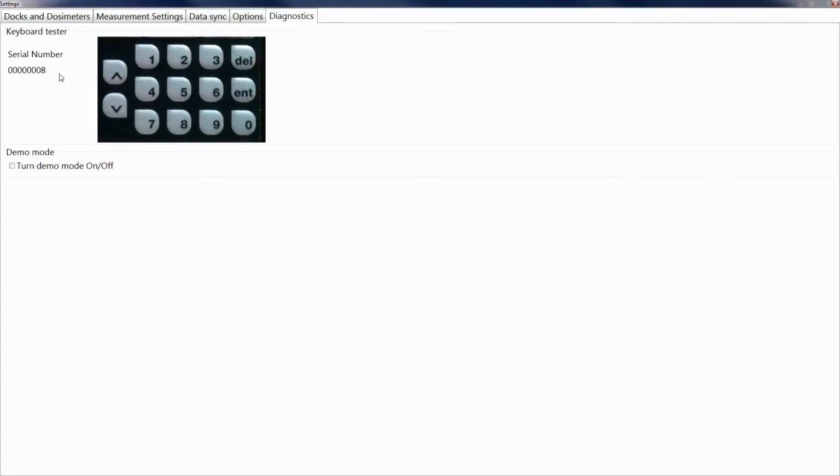The next option is demo mode. This allows you to activate a dosimeter that has not yet transitioned to trickle charge. It is recommended that this stays off, as activating a dosimeter before it has transitioned will result in reduced battery life, as well as a reduced runtime.